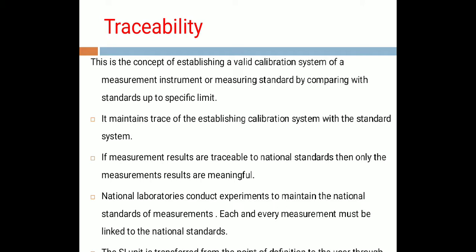Traceability. This is the concept of establishing a valid calibration system of a measurement instrument or measuring standard by comparing with standards up to a specific limit. It maintains traces of the established calibration system with the standard system. If the measurement results are traceable to national standards, then only the measurement results are meaningful. National laboratories should conduct experiments to maintain the national standards of measurement. Each and every measurement must be linked to the national standards. So traceability means we have to check the traces of the comparison of the measuring instrument with the standard instrument which represents the national standards.